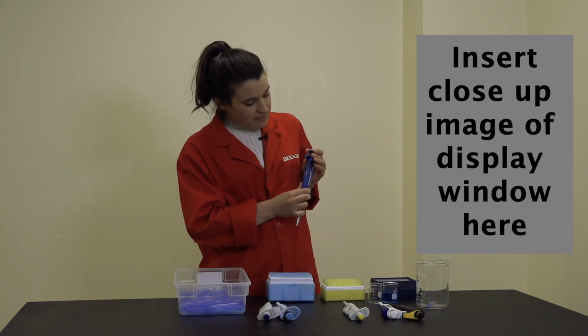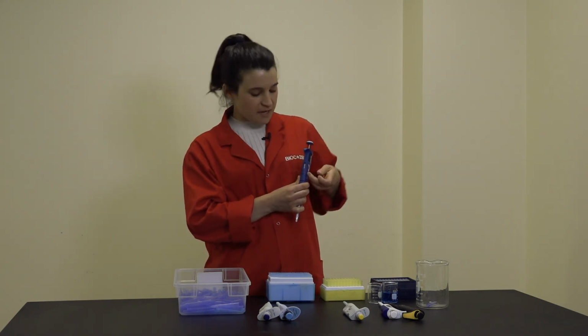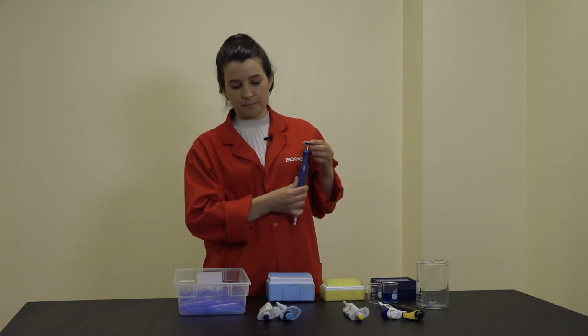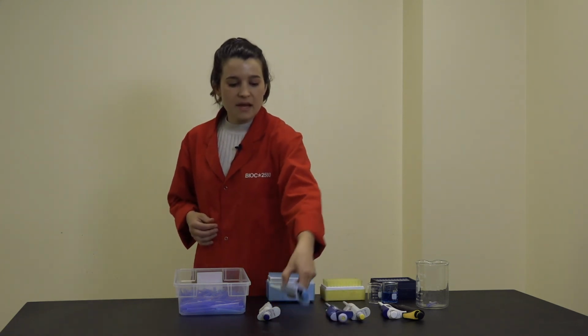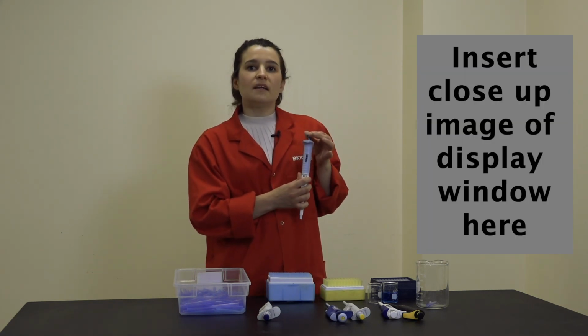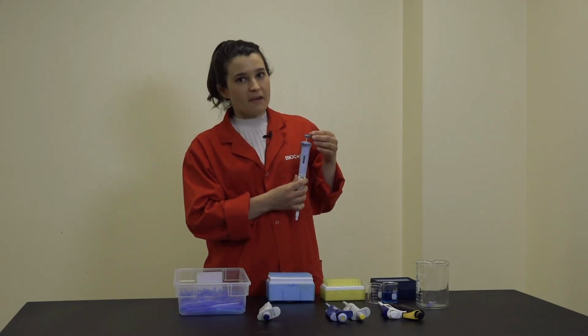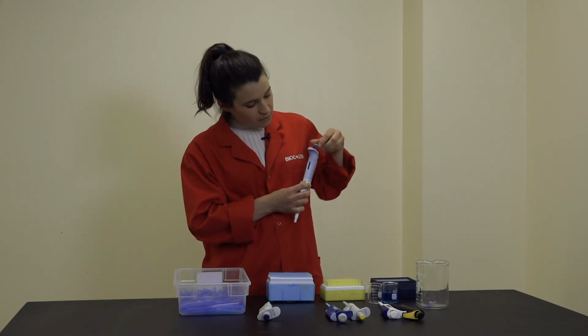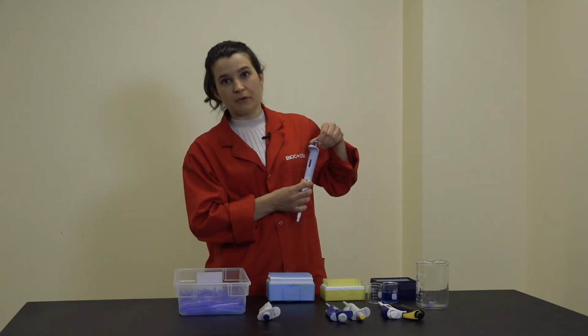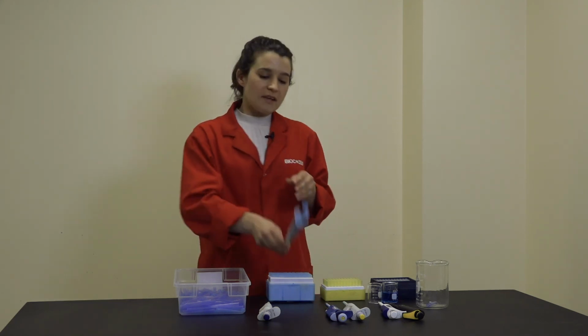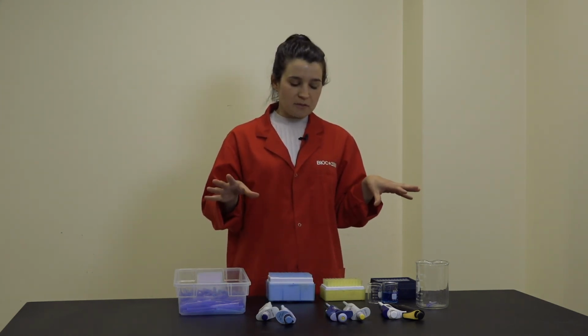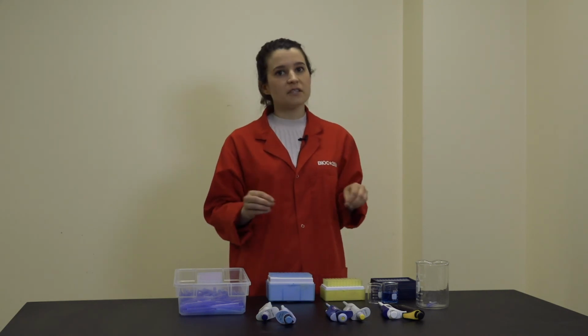Here's another P200, which in fact doesn't have numbers to indicate the first decimal place, but instead uses these markings along the bottom. Finally, we have a P1000, which actually goes up by increments of 5 microliters, and you use the markings along the bottom to select single microliter increments. So as you can see, the different brands and different volumes can differ a little bit in terms of how they display the volume, so make sure you pay extra attention to this before you begin using your pipette.